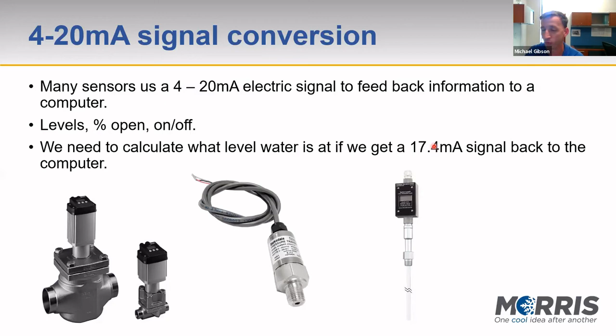We can think of this as a percentage — full is 100%, and empty is 0% in this example. They've got a nice graph going on here with the y-intercepts, showing 4 milliamps here, 20 milliamps here, and 100% open. Run is the percentage, and rise is the amperage.